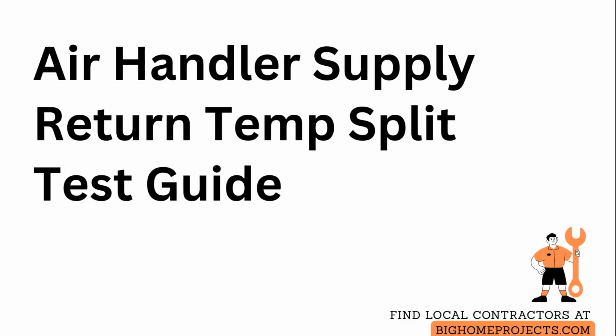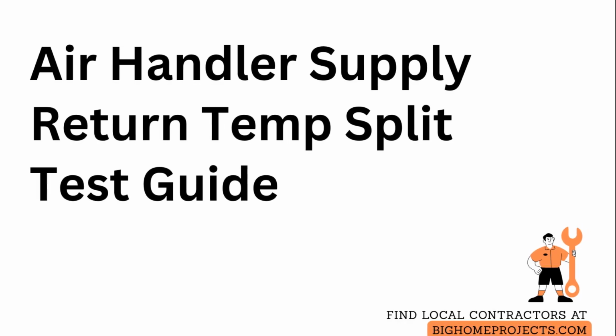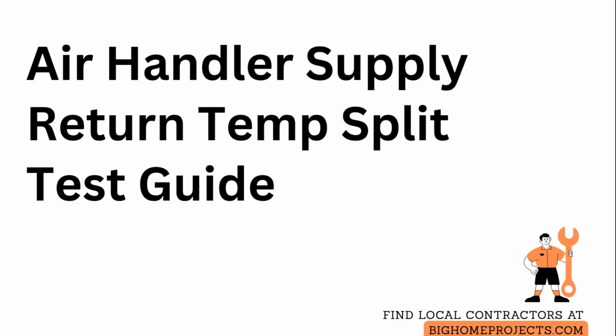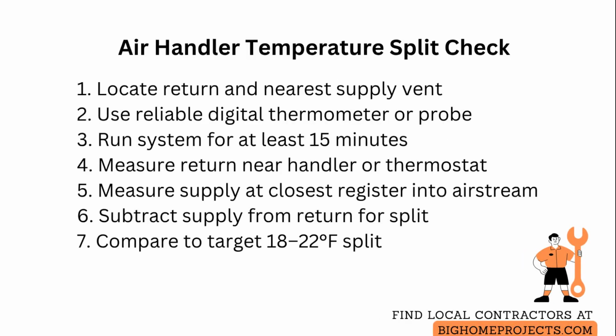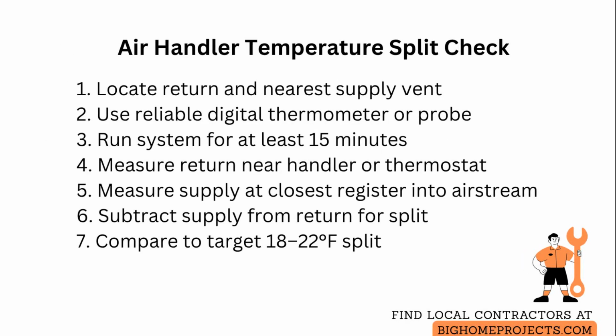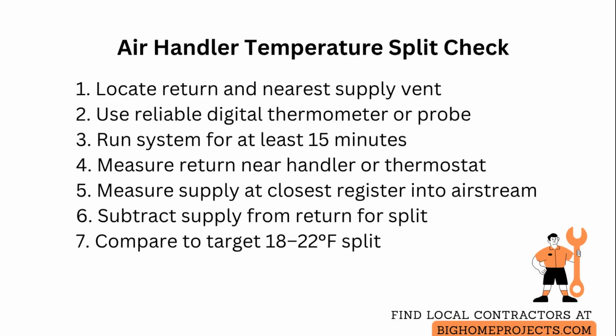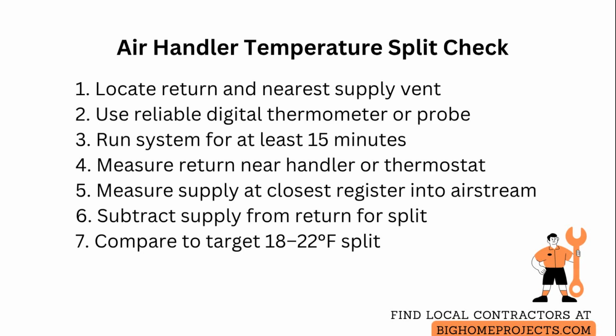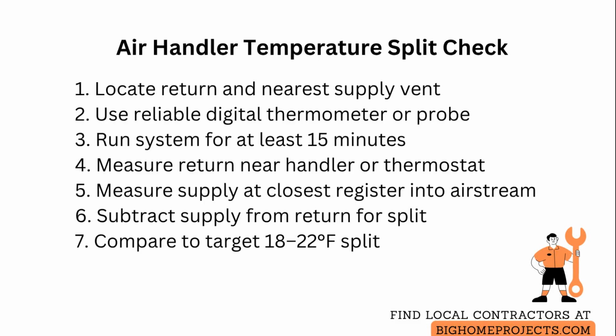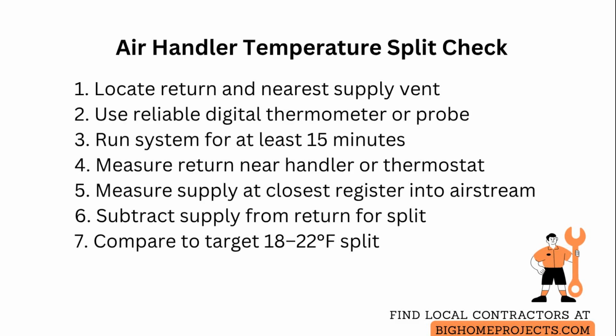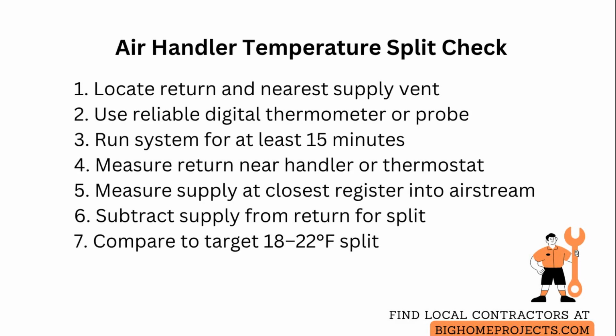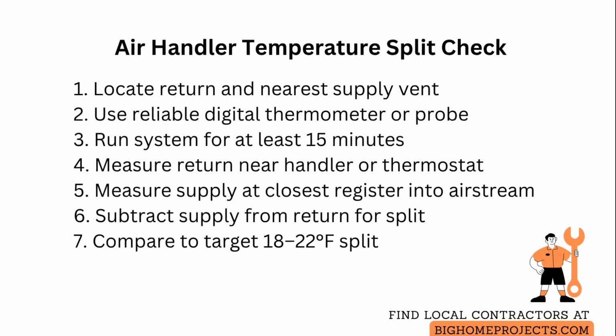Measure the temperature split by comparing the thermostat return air to the nearest supply vent for a clear read on cooling effectiveness. Start by locating the return air path and the nearest supply vent for the conditioned space you are testing. Use a reliable digital thermometer or probe and allow the system to run for at least 15 minutes at a steady cooling call so readings stabilize.